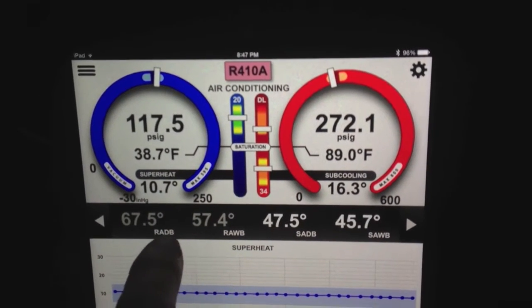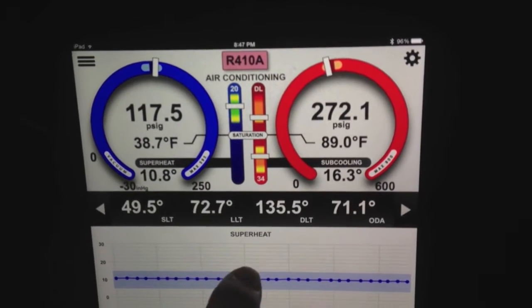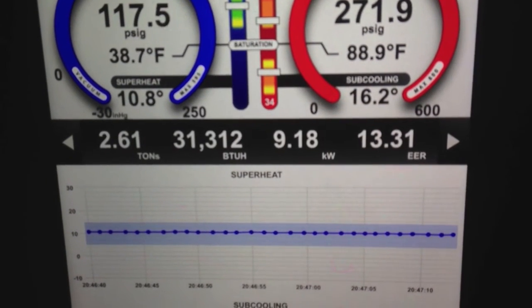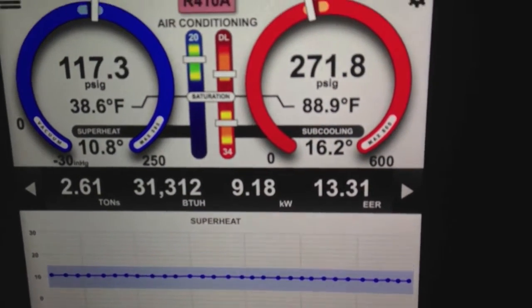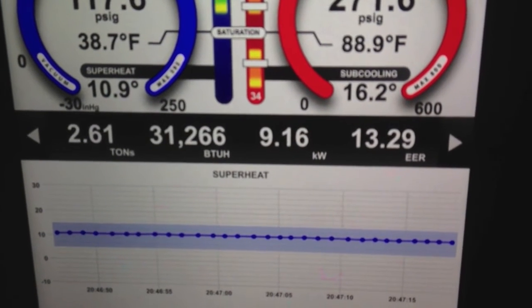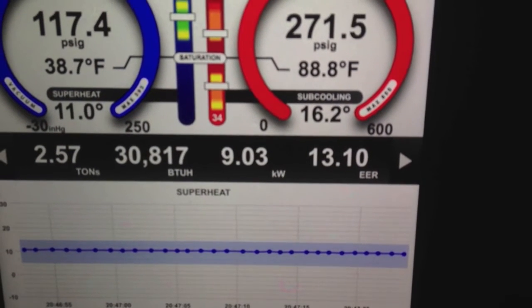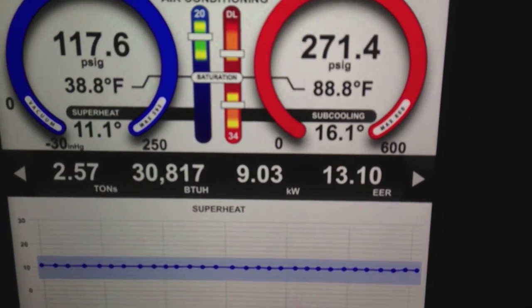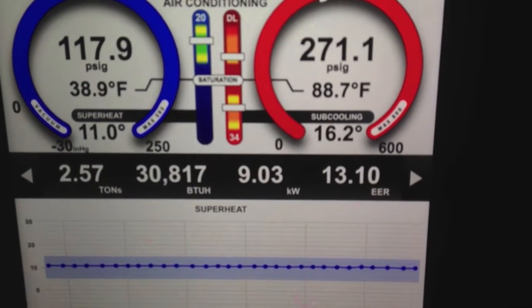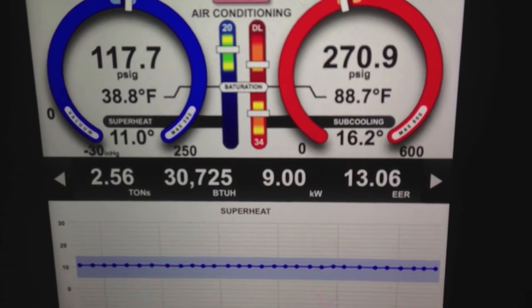You can see those are coming in in real time. Right on the bottom of the I-manifold display is our BTU. So we're doing 2.6 tons of cooling — 2.6 tons, 30,817 BTUs at 13.10 EER. The 9.03 KW is simply the BTUs turned to kilowatts — it's just a metric reading of that. You can see that's updating in real time as we go.